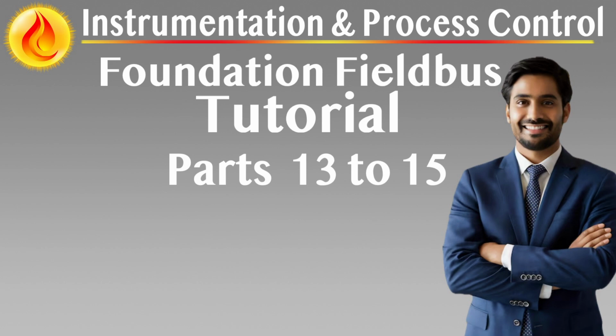All components, Type A shielded twisted pair cable, terminators, junction boxes, field barriers, segment couplers, and device mounting hardware, must be confirmed against approved specifications and drawings. Cables must be inspected for continuity, correct labeling, and compliance with insulation, shielding, and capacitance requirements per IEC 61158-2. Only approved and tested components shall be deployed to the field.